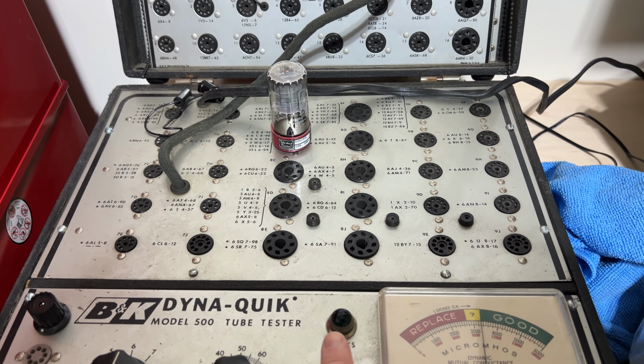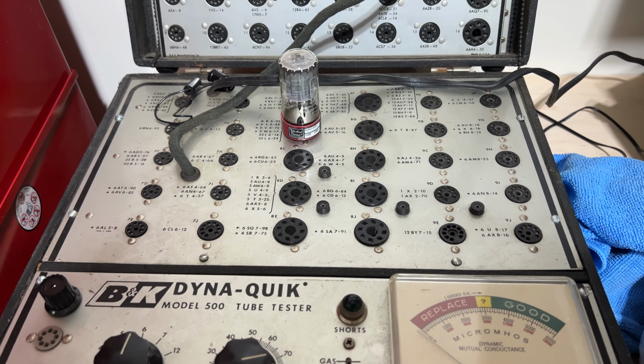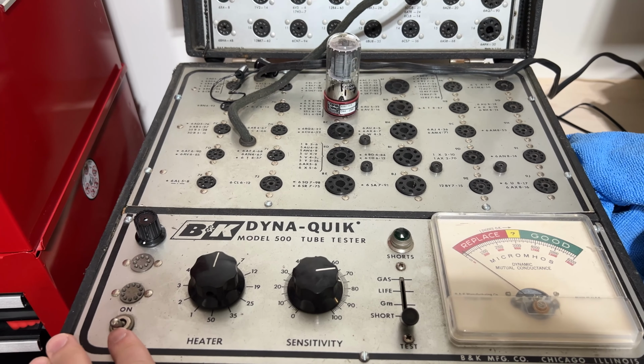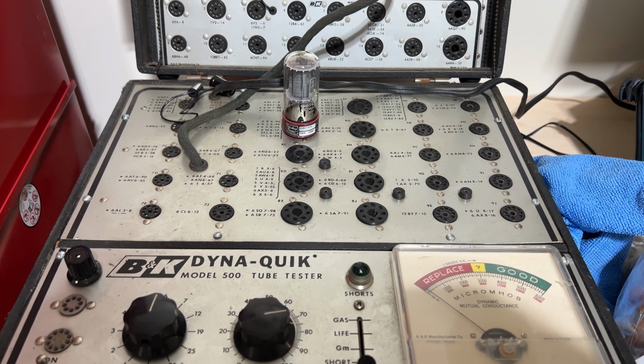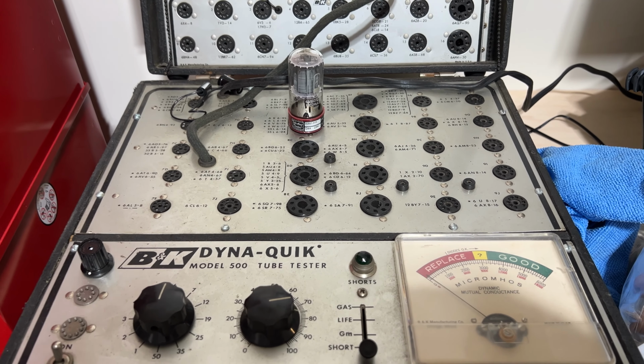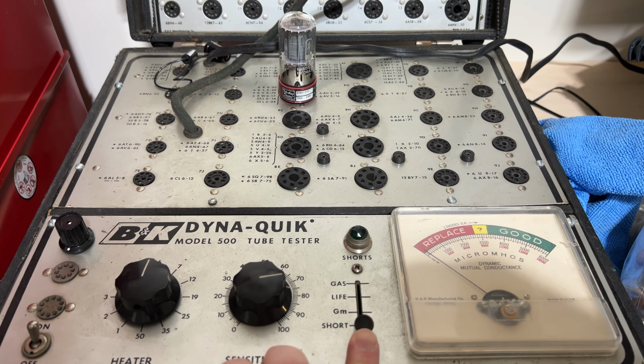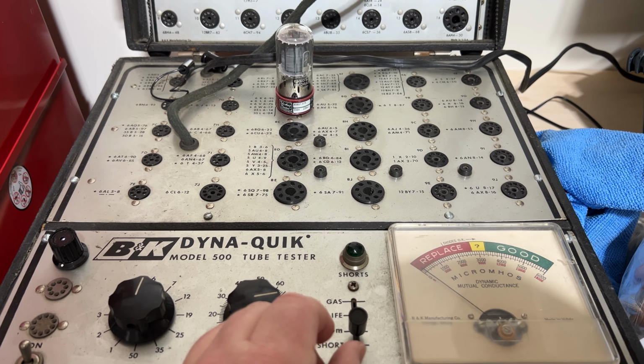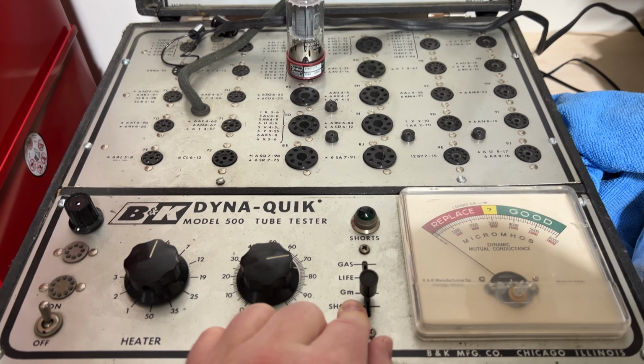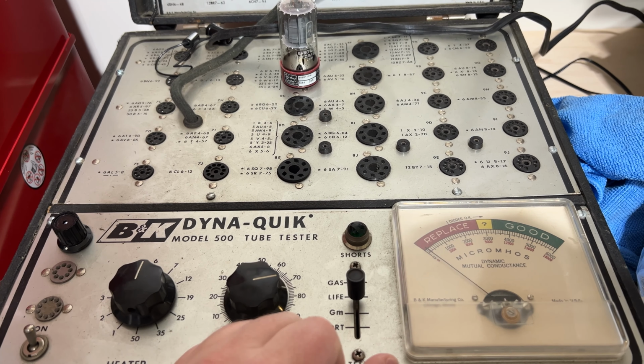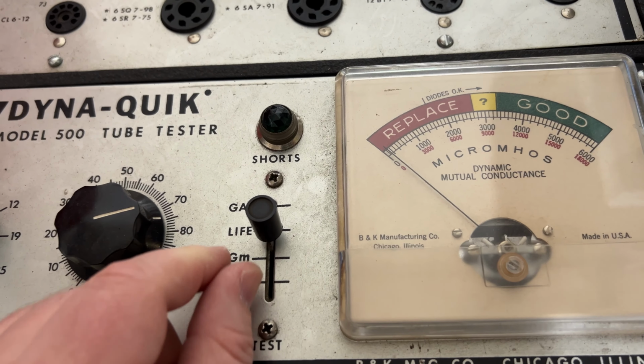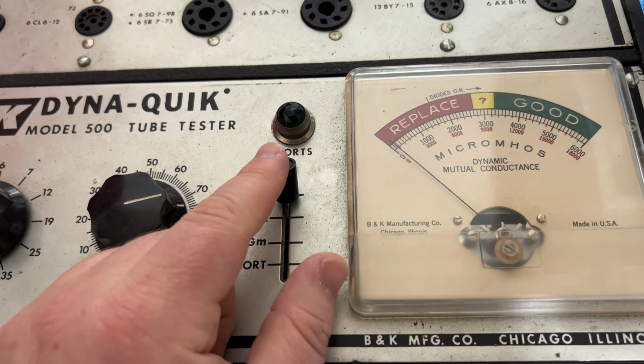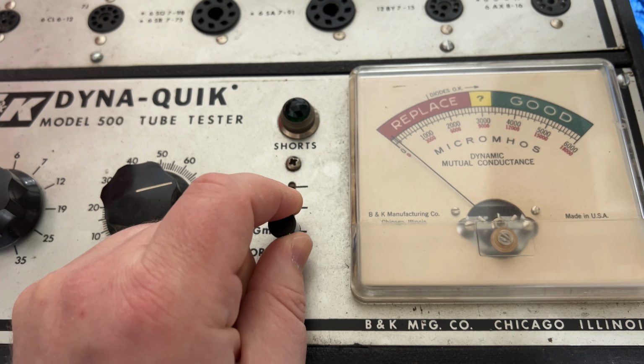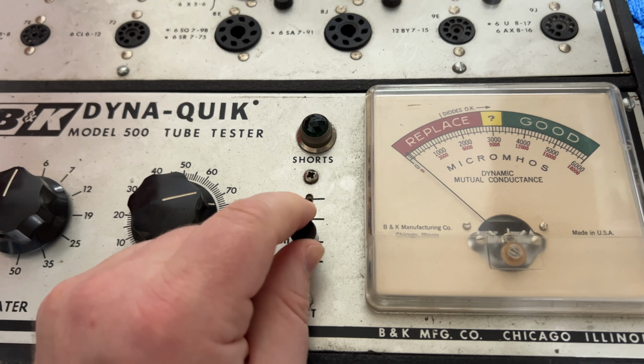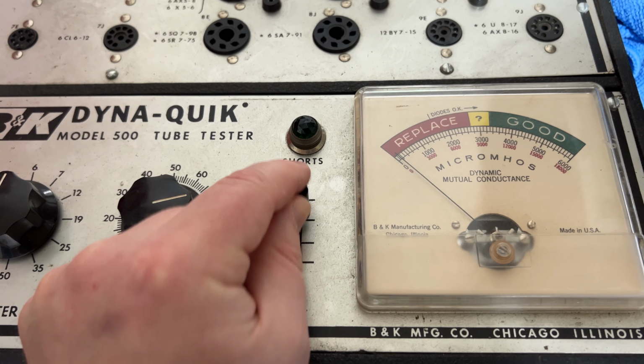Now let's see what happens when we plug in the one that looks like it's probably problematic. Okay, so same socket, same settings. Firing this up. And now we don't have a short circuit. But if I go to our GM setting, it's nothing. If we go to our life, no life. Nothing left. Gas. So this one's just showing up with nothing on the board, which means we've got a failed tube.